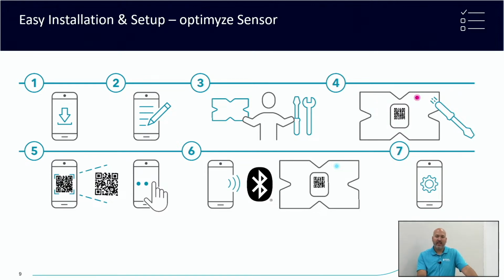So you hover the magnet over the LED, or there's a little Bluetooth icon there. You hover it over there for a few seconds. The LED should start to flash pink. That's letting you know that it's in pair mode or configuration mode. You'll go to your mobile device, and within the optimyze application, you will scan the QR code that's on the front of the optimyze sensor, or you have the ability to manually enter its serial number. So underneath the QR code, there will be a serial number listed. But once you do that, the LED on the optimyze sensor should flash blue. That's letting you know that you have successfully made a good connection to the unit. That Bluetooth connection was established.